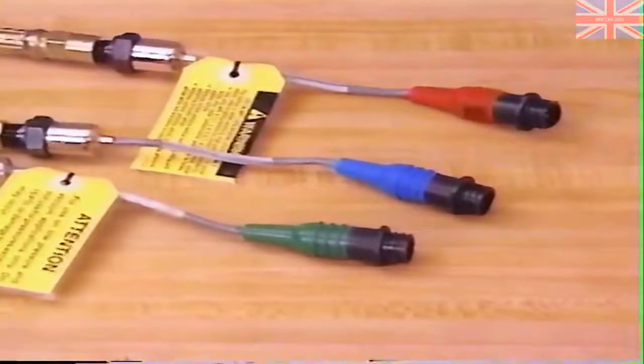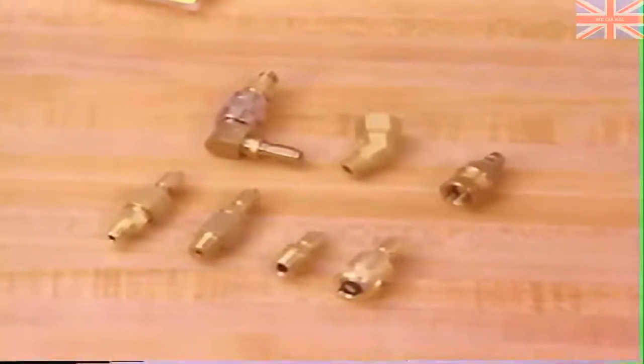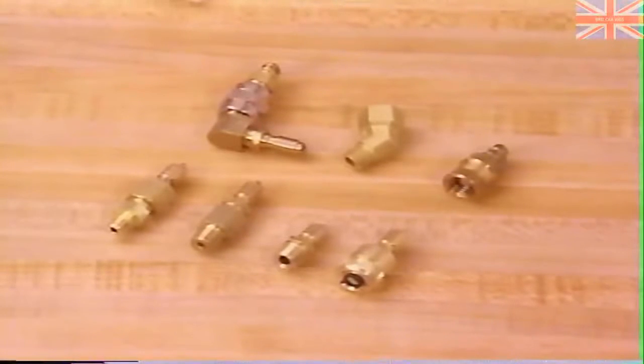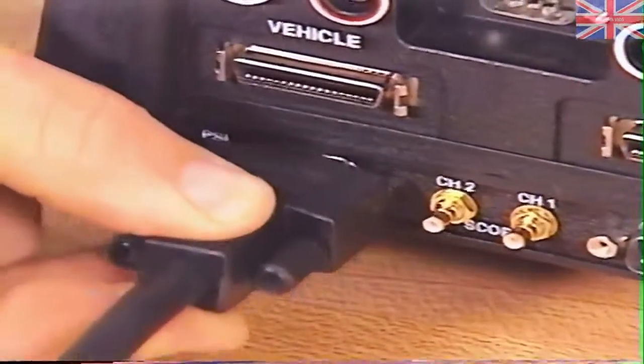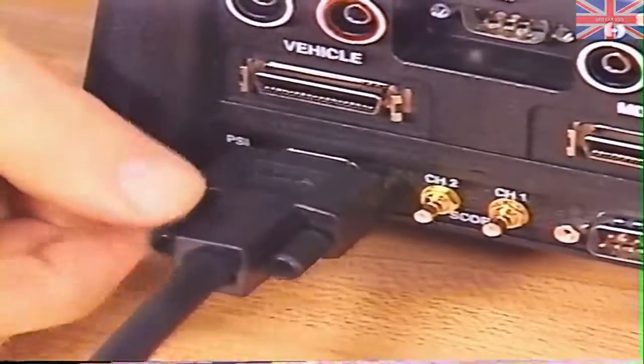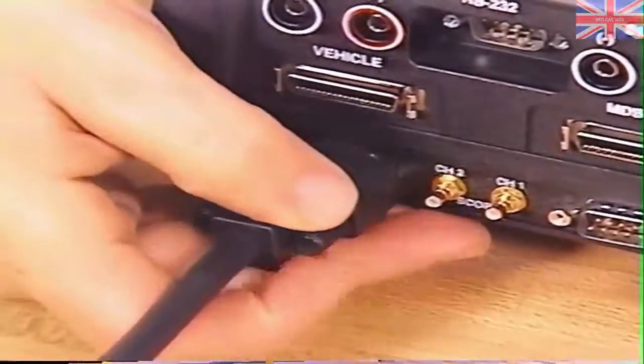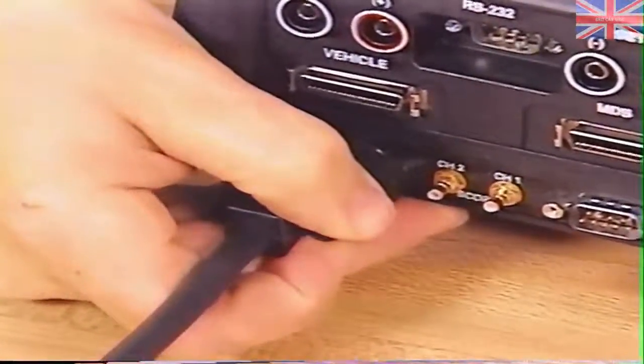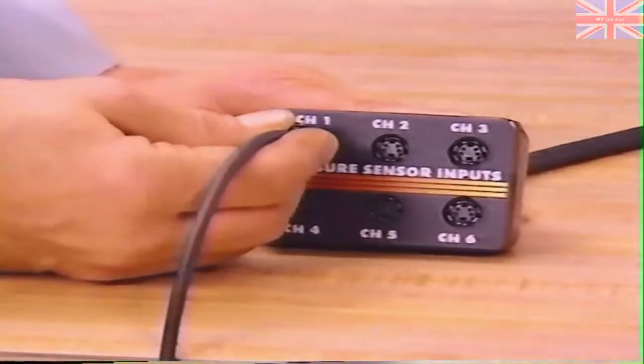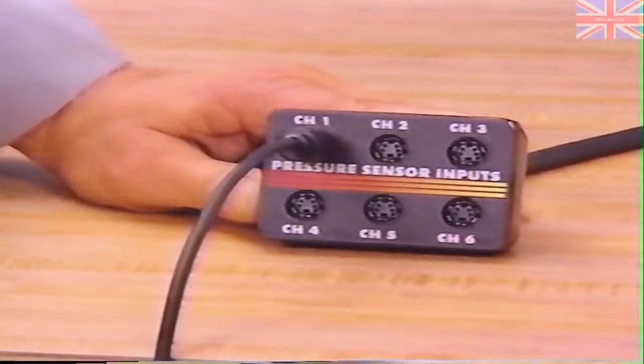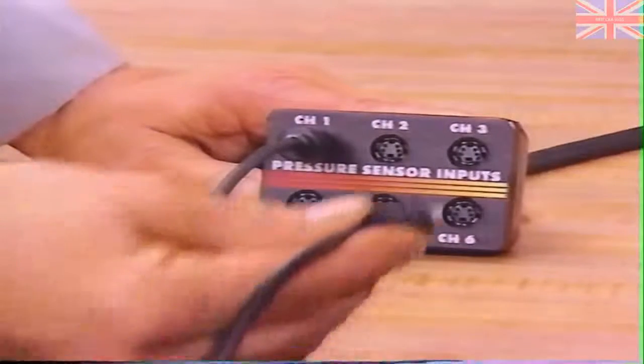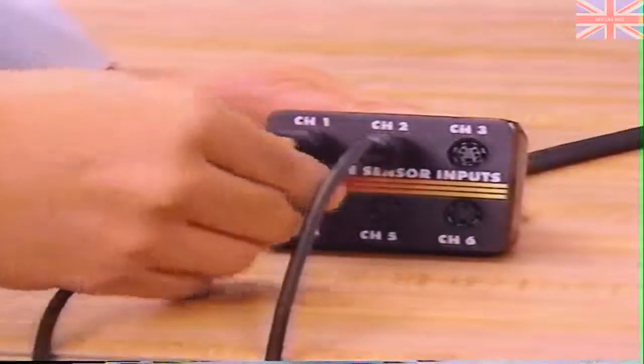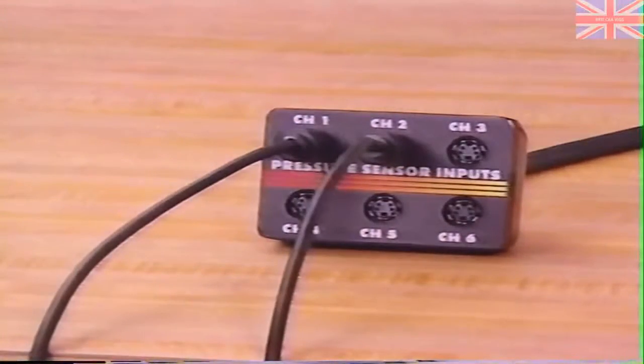In addition to the transducers, the accessory kit contains a variety of pressure fittings, allowing the pressure tester to be used in most applications. Now let's take a look at the other items in the accessory kit and see how they're used with the digital pressure tester. The 6-input cable connects to the PEP module at the connector that is marked PSI. Be sure to tighten the thumb screws to properly seat the cable in the connector. A 12-foot extension cable that is supplied in the accessory kit connects to the keyed head of the 6-input cable. If you're testing more than one pressure port, you'll need another extension cable.